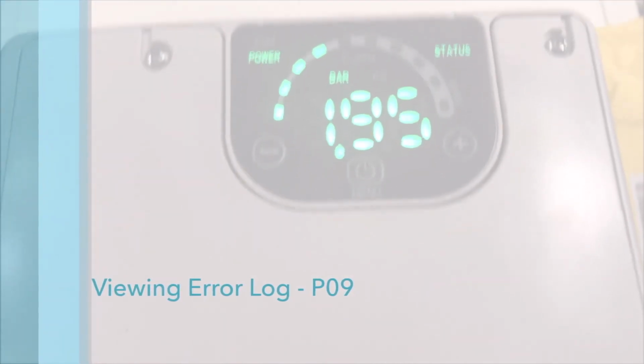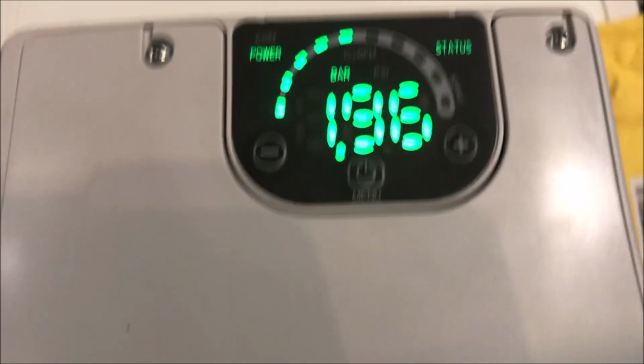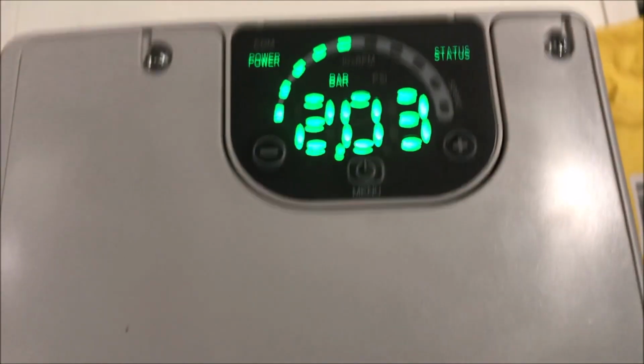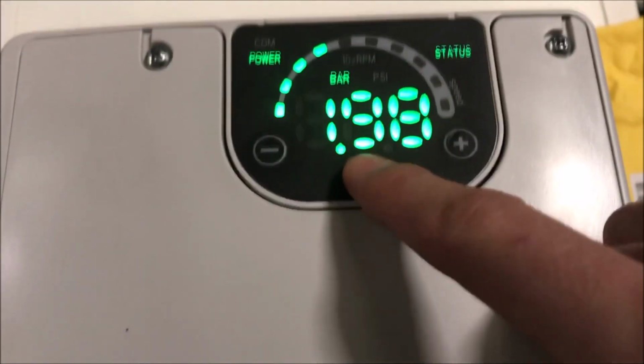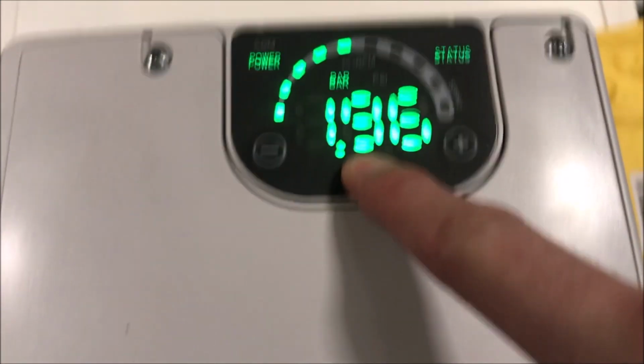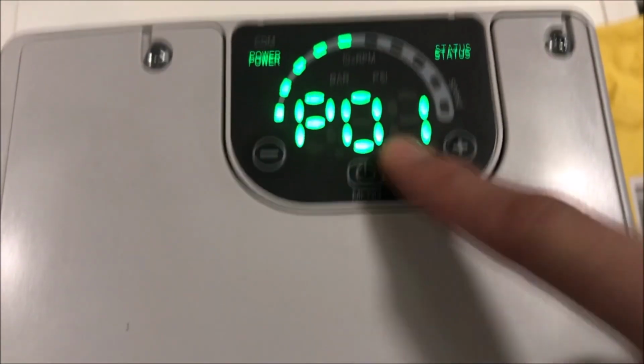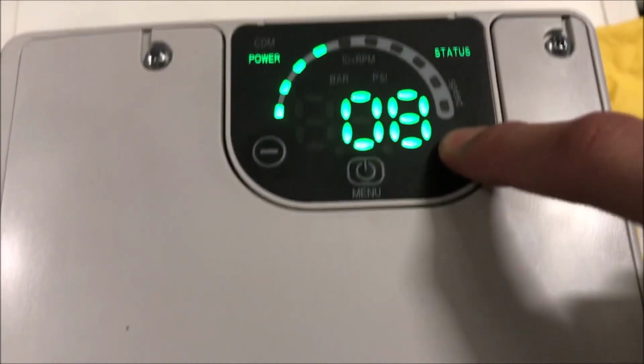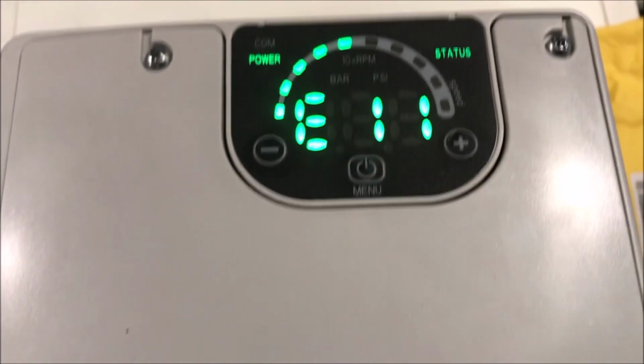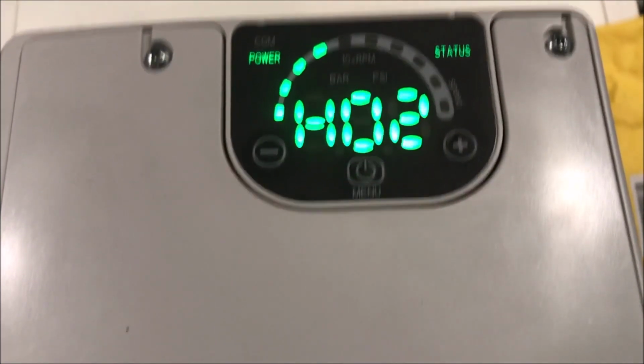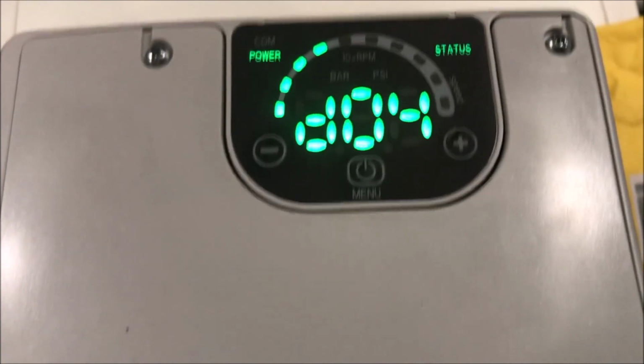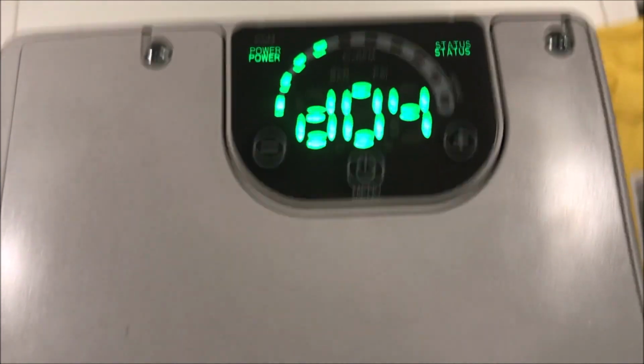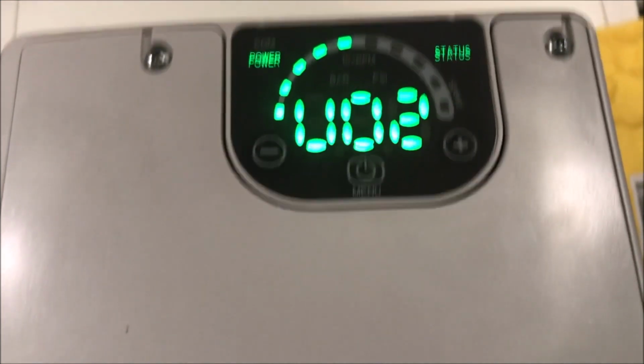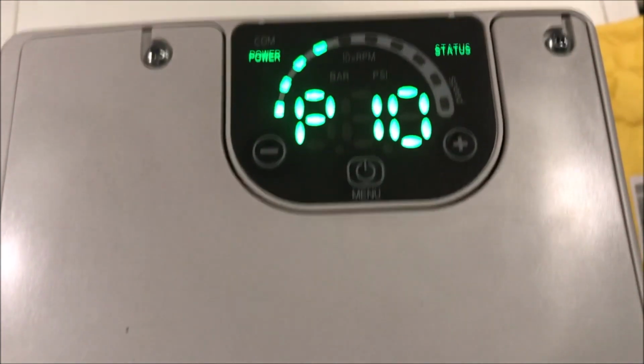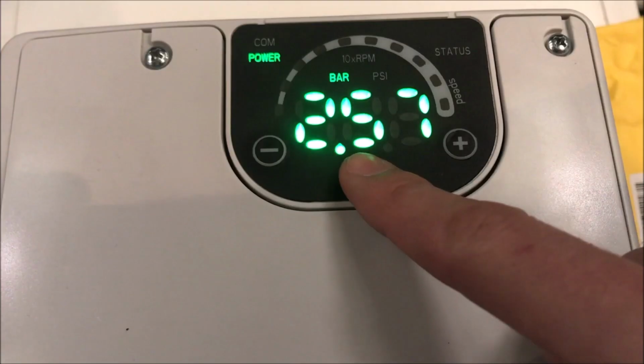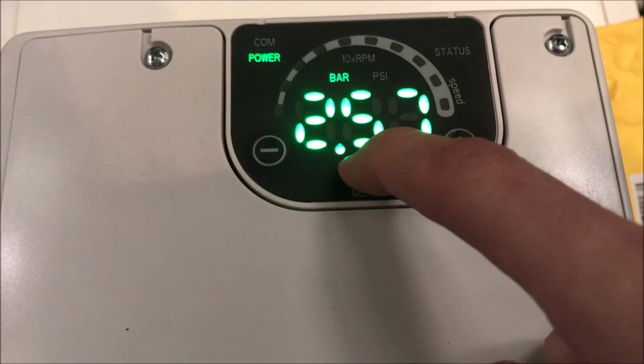The ESM drive stores the last 4 occurring errors. The log of the most recent error can be found at parameter 9. The screen will then cycle the error code along with the hour, the day, and the week in which the error occurred. The second, third, and fourth errors are stored in parameter 10, 11, and 12.